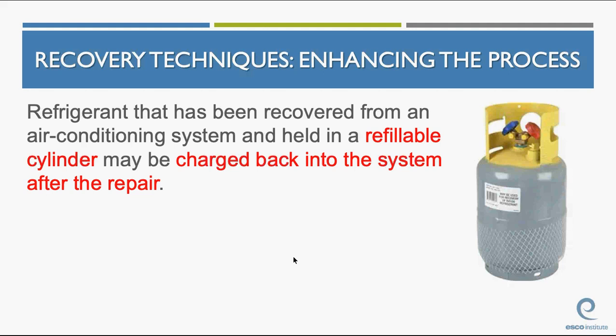Refrigerant that has been recovered from an air conditioning system and held in a refillable cylinder may be charged back into that system after the repair. Okay, in other words, if I'm making a repair, changing a metering device, changing a filter dryer, something like that, I'm allowed to put that refrigerant back into that system. When is one time you do not want to reuse that refrigerant?